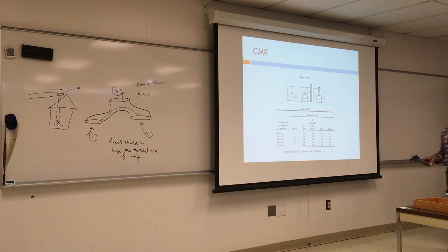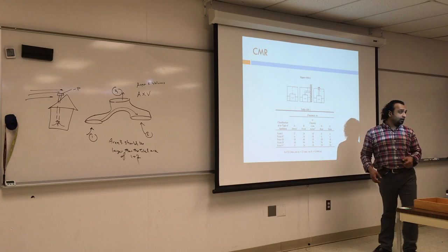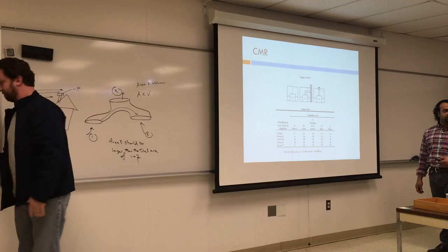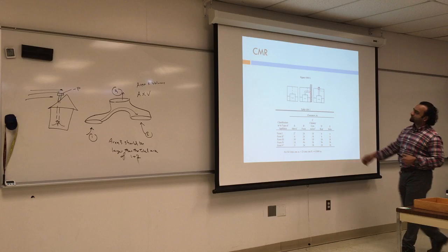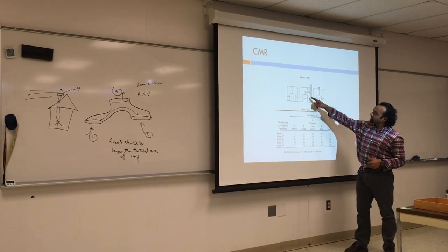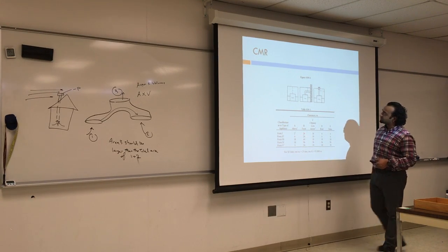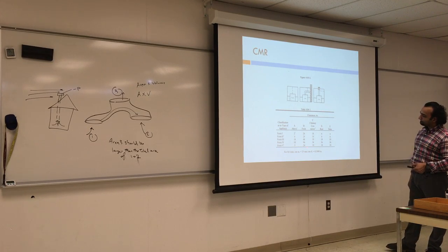This is from the CMR, that's the Massachusetts code. I think it's 571 or something. I have it on Blackboard. These are the clearances based on the types, A, B, and C, 2 feet front, 24 inches, and this is the configuration if you vent it through a wall, or if you vent it upstairs through the ceiling, and they have it in inches and meters.